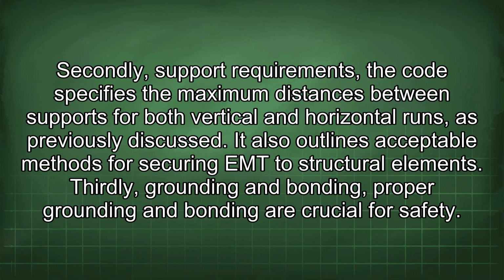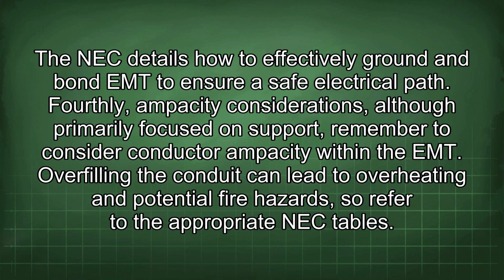Secondly, support requirements. The code specifies the maximum distances between supports for both vertical and horizontal runs, as previously discussed. It also outlines acceptable methods for securing EMT to structural elements. Thirdly, grounding and bonding. Proper grounding and bonding are crucial for safety. The NEC details how to effectively ground and bond EMT to ensure a safe electrical path. Fourthly, ampacity considerations. Although primarily focused on support, remember to consider conductor ampacity within the EMT. Overfilling the conduit can lead to overheating and potential fire hazards, so refer to the appropriate NEC tables.